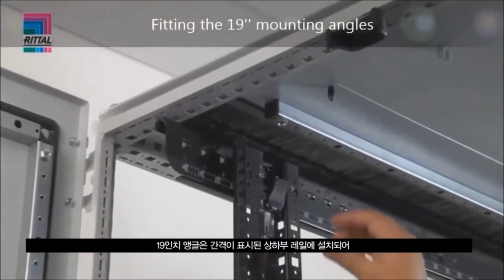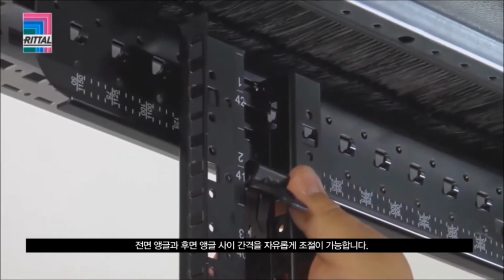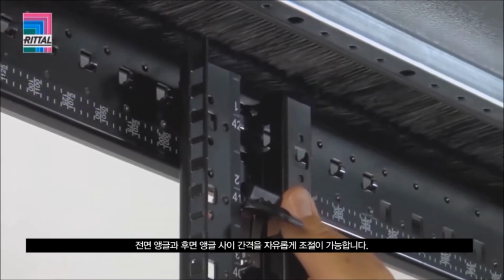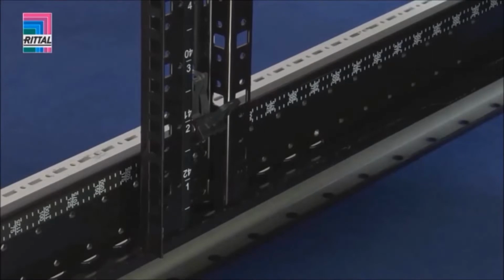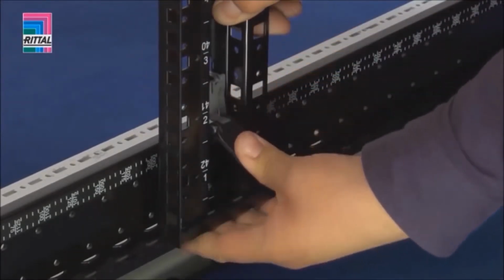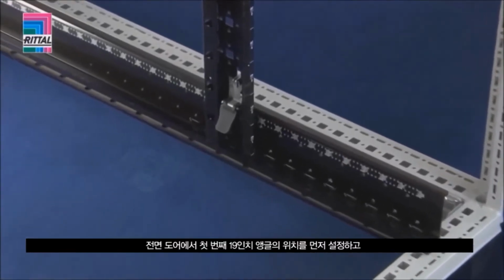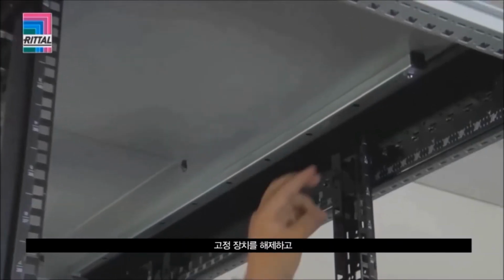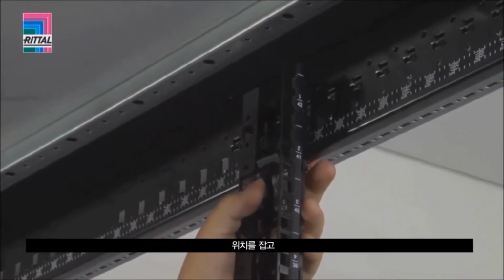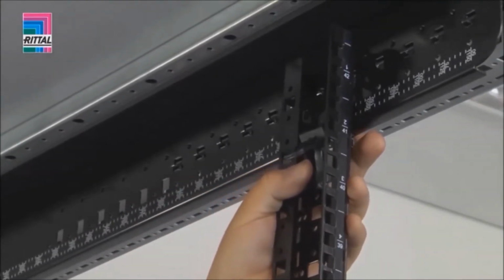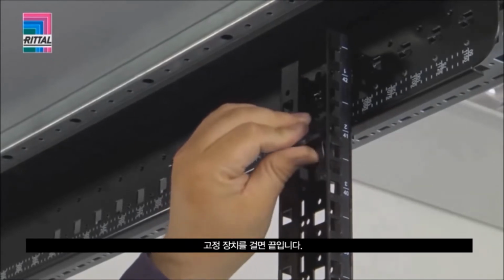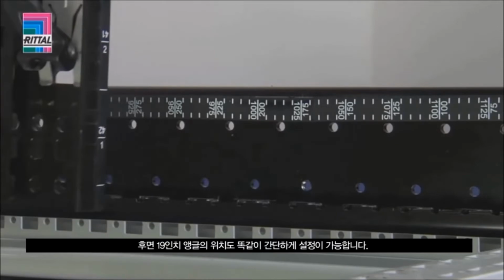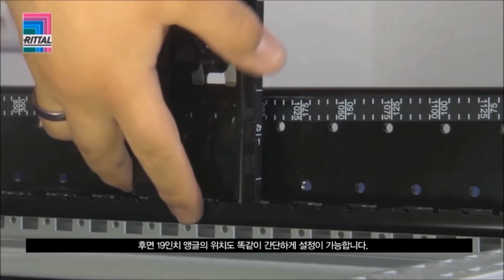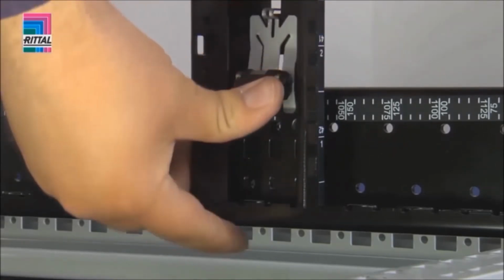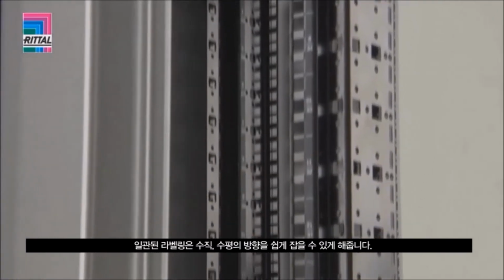The front bar is inserted into the pitch pattern, while the rear bar is freely positionable, so that any required distance between the 19-inch levels can be achieved. Adjust the distance from the front door to the first 19-inch level. Simply loosen the attachments. Position. Latch home, and it's done. Positioning the rear 19-inch mounting level is equally straightforward. The consistent labeling allows easy orientation, vertically and horizontally.